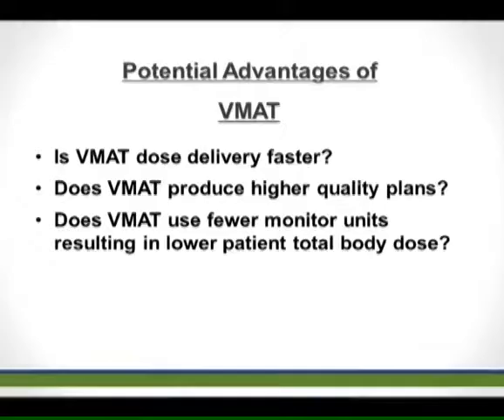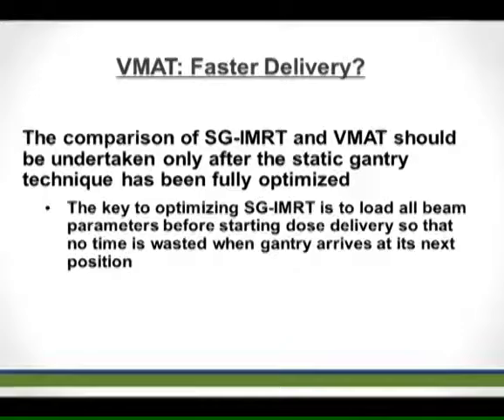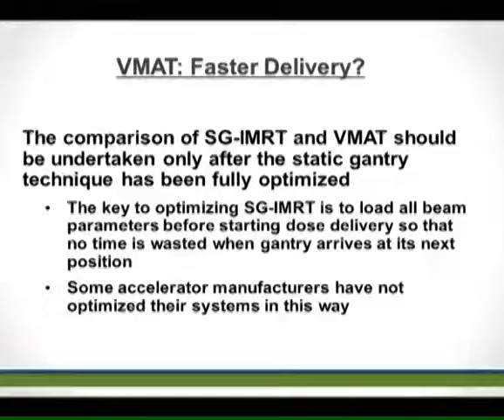We ask ourselves: can we increase delivery efficiency with VMAT? Can treatments be delivered faster? Do they produce better plans? Do they actually use fewer monitor units? Fundamentally, the implementation of static IMRT delivery has not been optimized to its limit, so it is not fair to directly compare delivery efficiency. However, in current implementations, VMAT delivery is actually a lot faster than static IMRT.